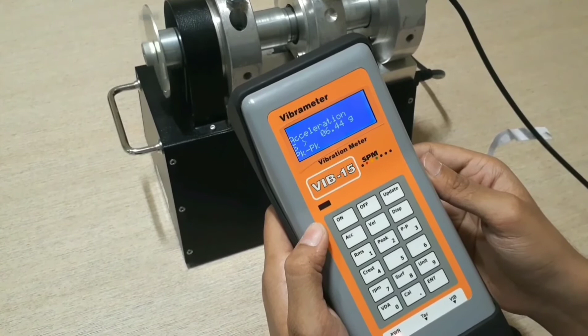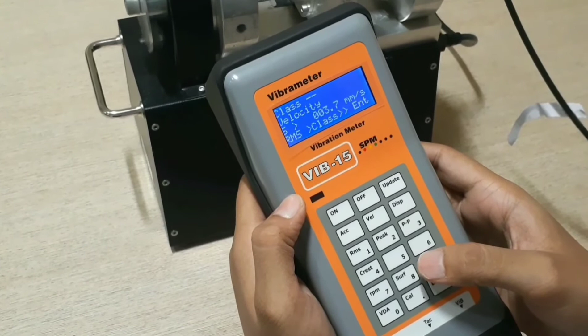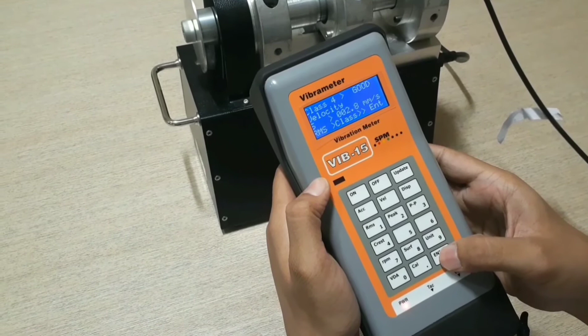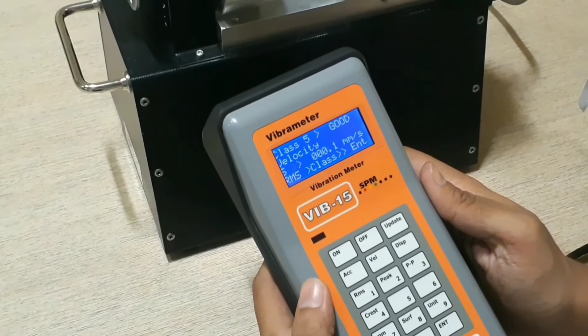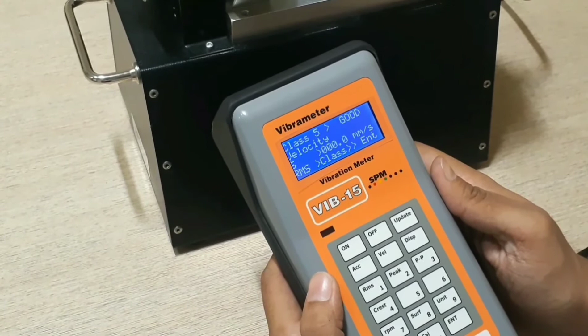Taking velocity readings. Right now, in order to take the velocity readings in RMS values, we need to enter classes. In order to enter classes, we need to press the enter button. It will shift the classes. In our vibration meter, we have class 1 to class 6. According to your industrial application, you can select from class 1 to class 6 and you can take the measurement.